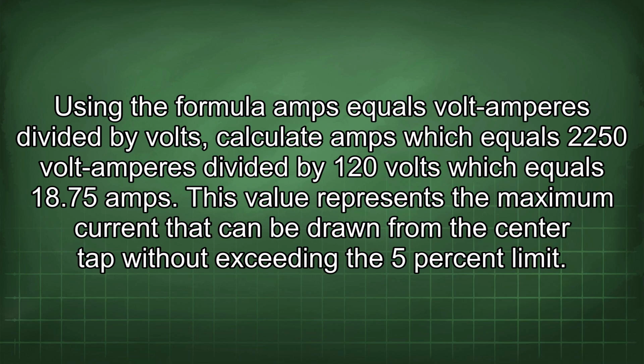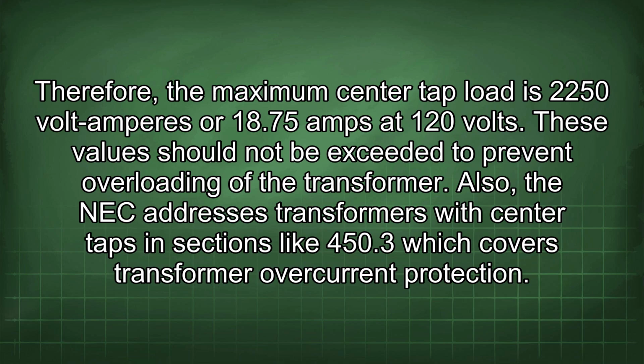Using the formula amps equals volt amperes divided by volts, calculate amps, which equals 2250 volt amperes divided by 120 volts, which equals 18.75 amps. This value represents the maximum current that can be drawn from the center tap without exceeding the 5% limit. Therefore, the maximum center tap load is 2250 volt amperes or 18.75 amps at 120 volts. These values should not be exceeded to prevent overloading of the transformer.